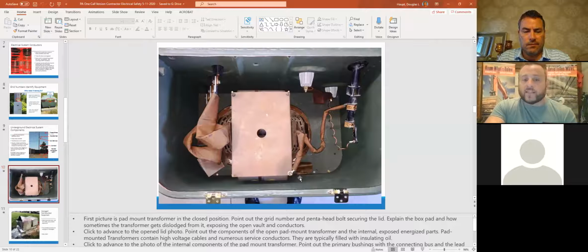Transformer, this is the back side of the underground transformer, the big green box. Inside this area, the front side is all the primary connections, and this is where the transformation happens. In the back, this is full of mineral oil today, and the reason we like to show this is you'll notice right here, this is the hot side. This is 7200 coming in, does its transformation, and this is the secondary bushings on this side.